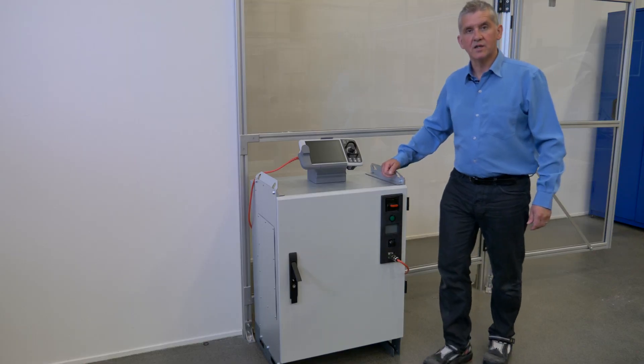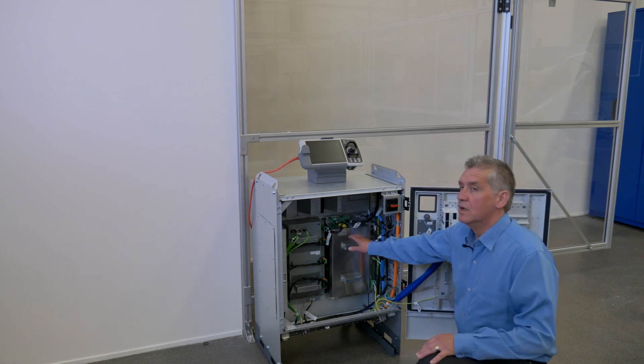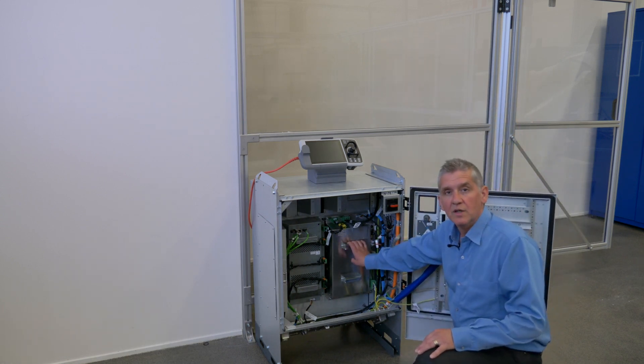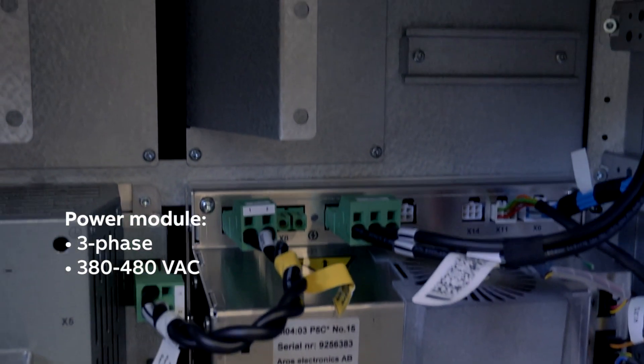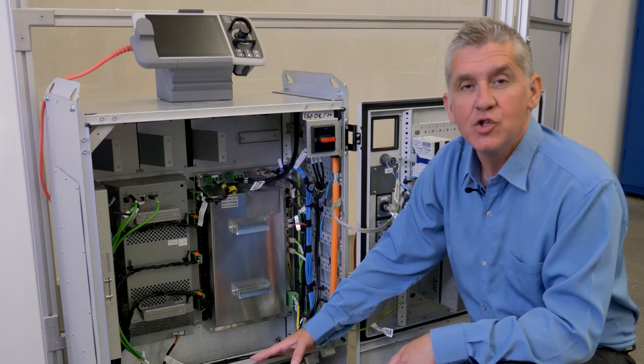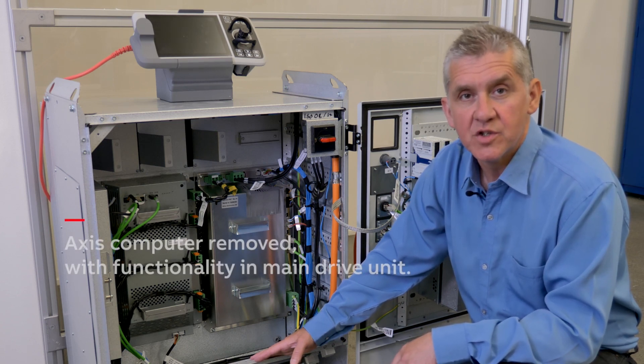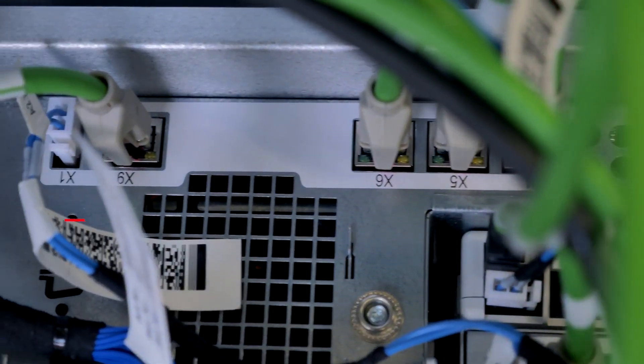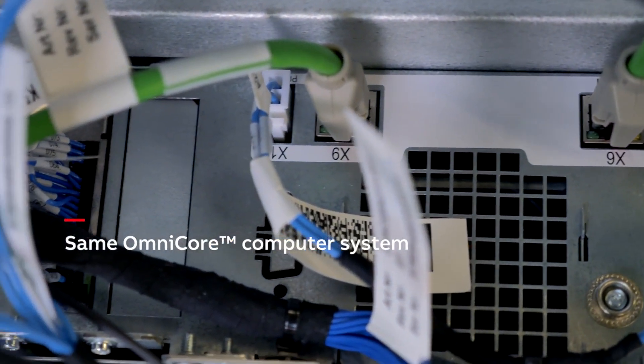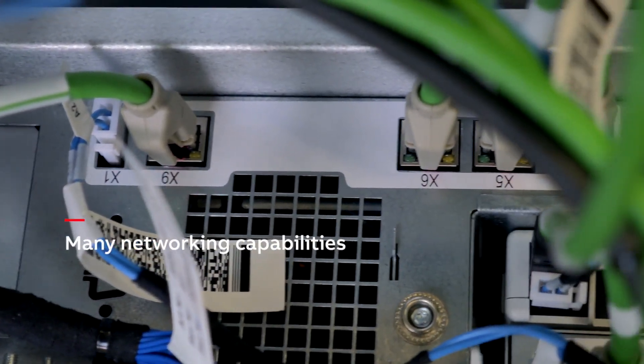Now, let's have a look inside the controller. This is the power module. It supports three-phase input from 380 to 480 volt. One new feature is that the axis computer is removed. Instead, the functionality is included in the main drive unit. The computer system is the same as in our other Omnicore controllers and comes with a lot of networking capabilities.